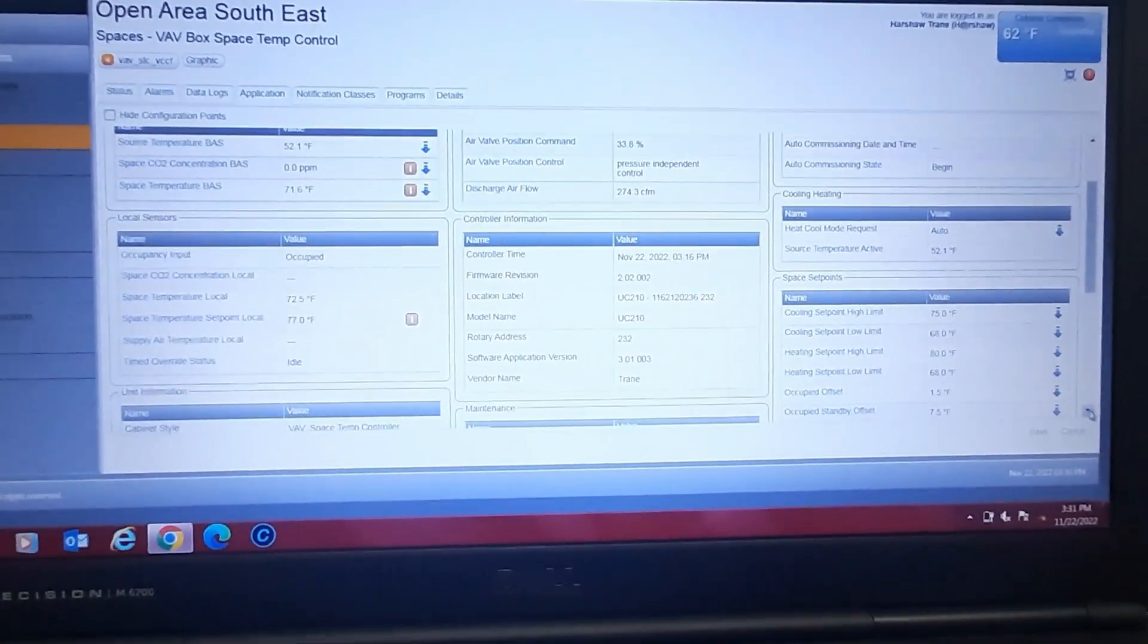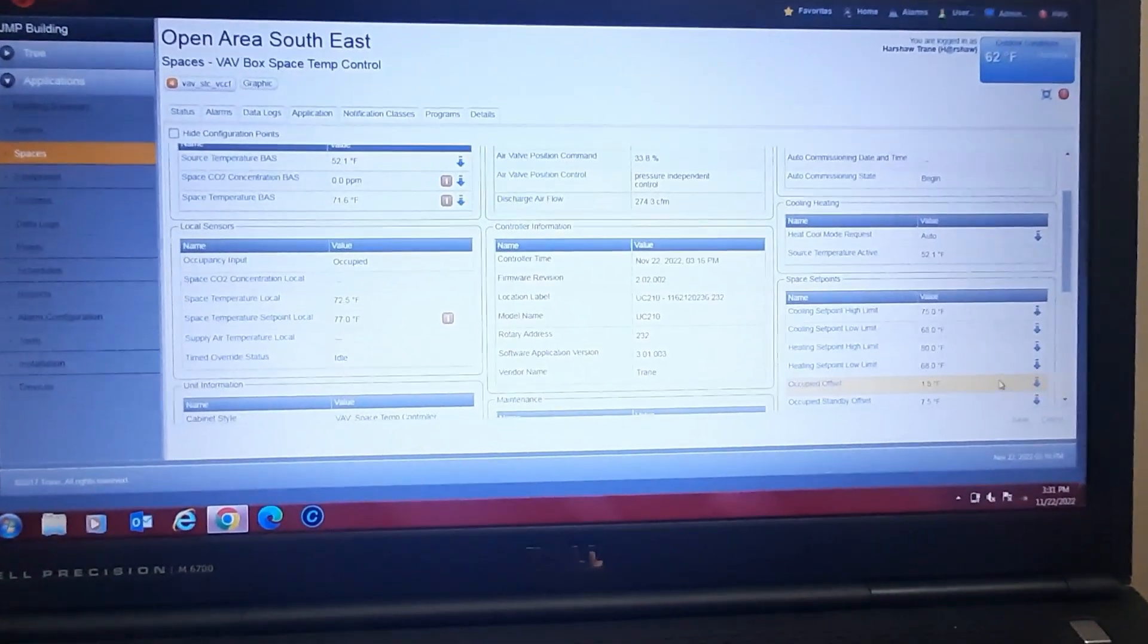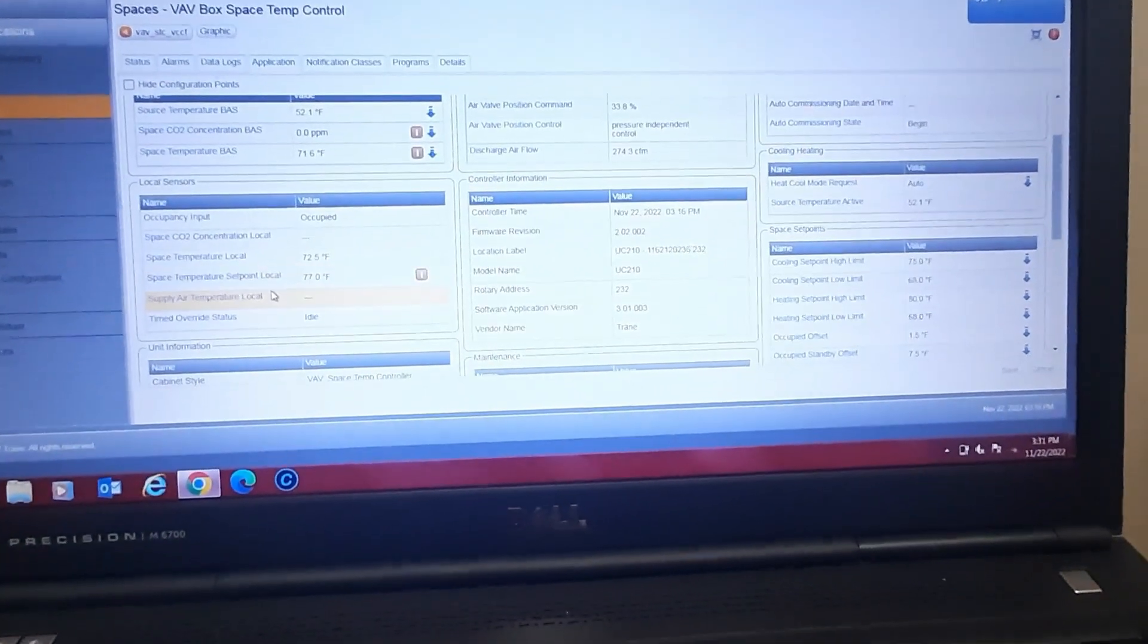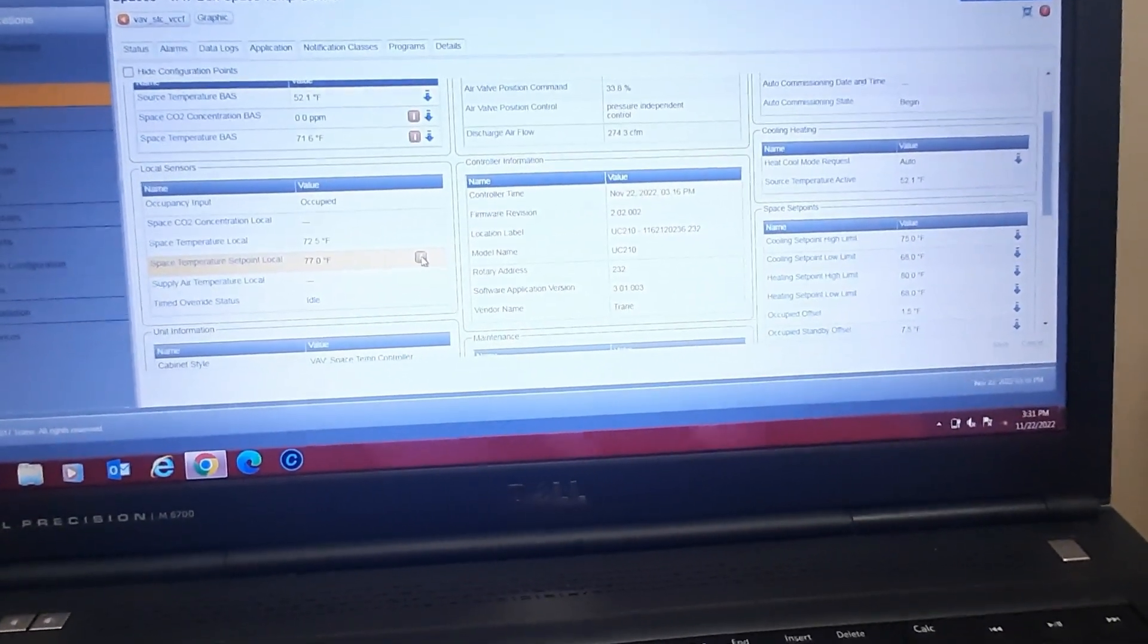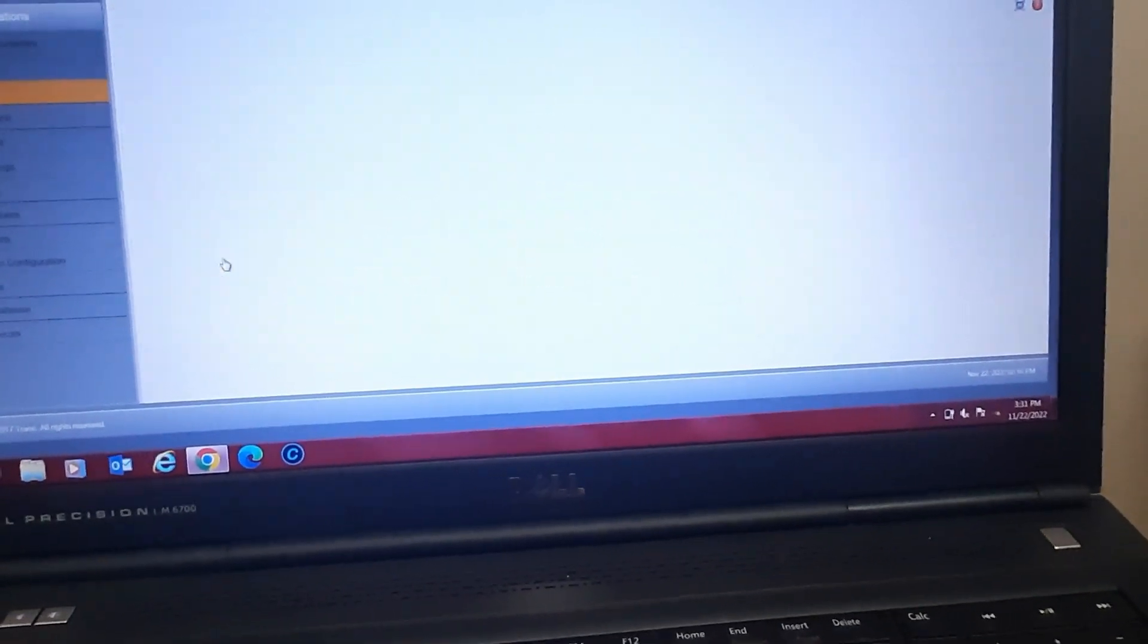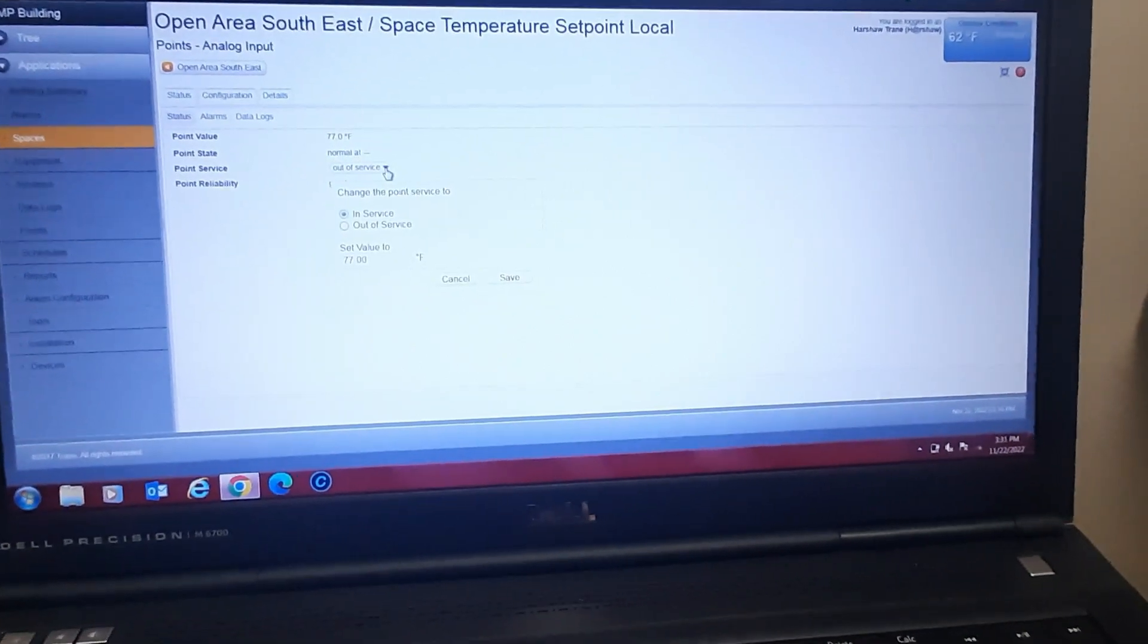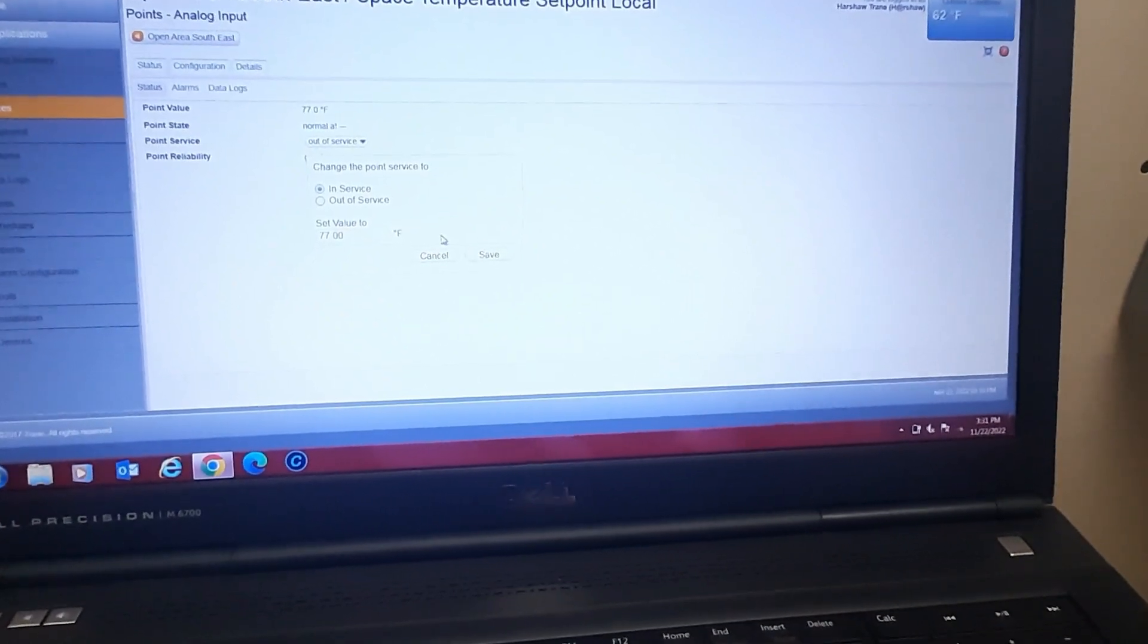So the last thing I found here is my temperature wasn't changing with the set point. Set point was enabled, but you can see space temperature set point local, these mean out of service, so we're going to want to go in here and put this back in service.